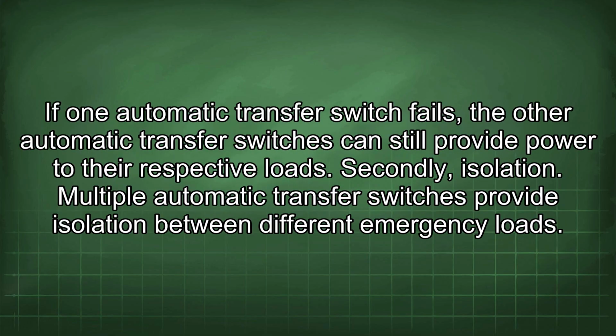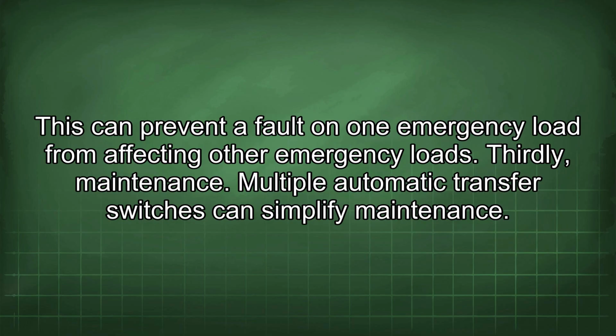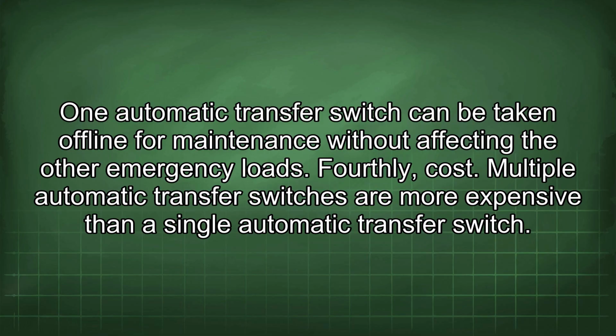If one automatic transfer switch fails, the other automatic transfer switches can still provide power to their respective loads. Secondly, isolation. Multiple automatic transfer switches provide isolation between different emergency loads. This can prevent a fault on one emergency load from affecting other emergency loads. Thirdly, maintenance. Multiple automatic transfer switches can simplify maintenance. One automatic transfer switch can be taken offline for maintenance without affecting the other emergency loads.